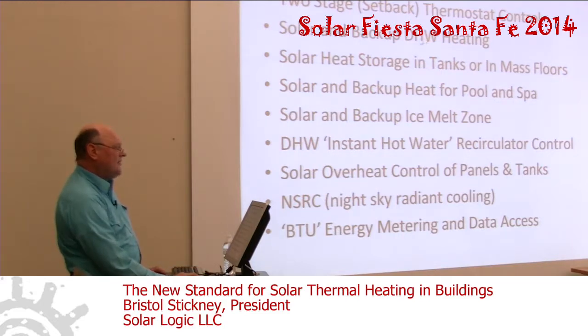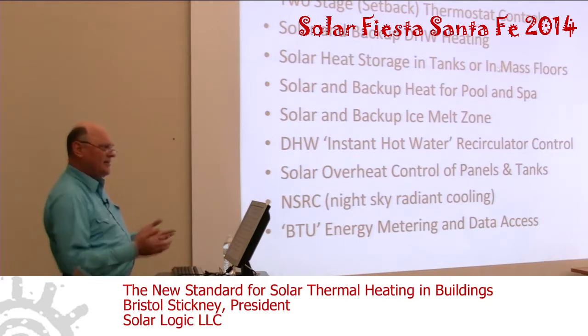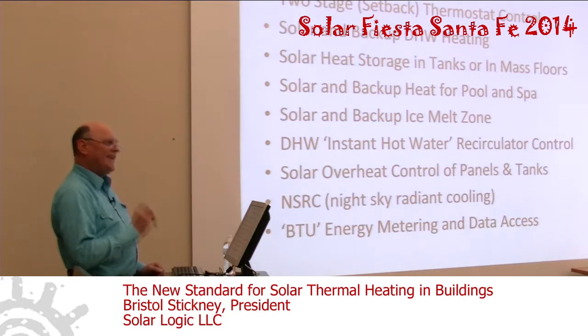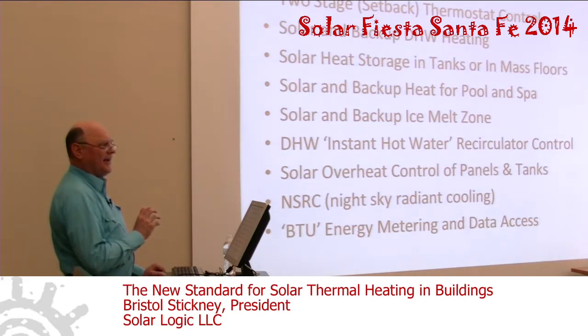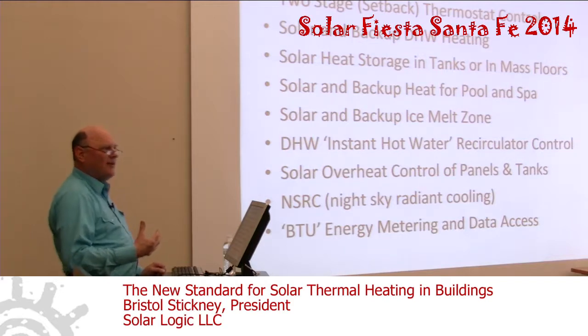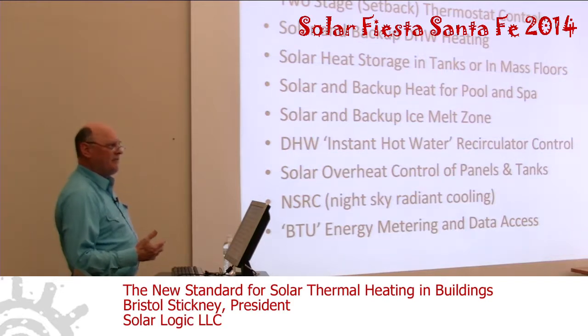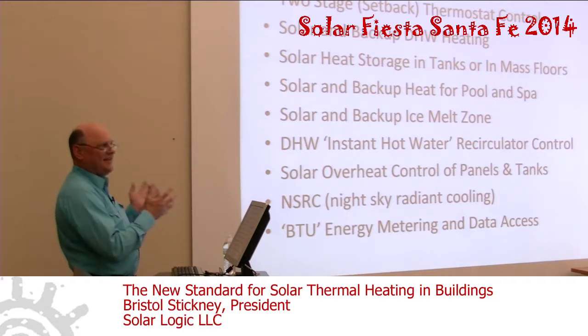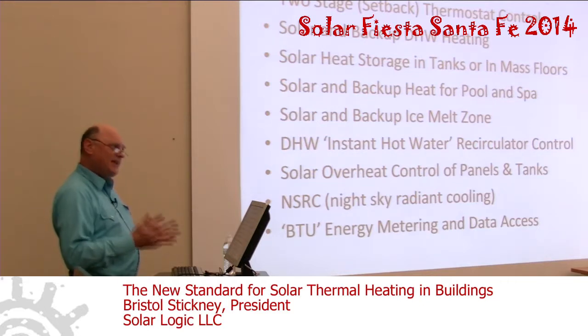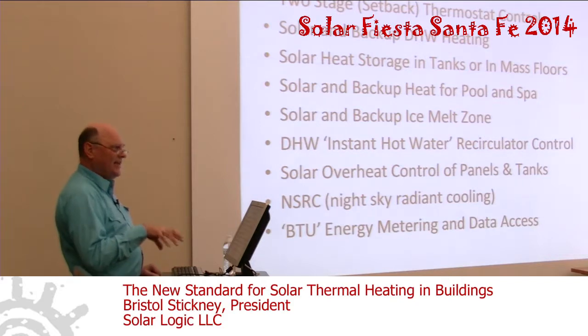You want the domestic hot water heater tank to be prioritized so that it gets solar first and the backup heat second. You want to be able to store heat not only in storage tanks, but also in any mass floors, like big concrete floors with heat being delivered into them, and control the heat stored in the concrete. And if you take that into account, sometimes you can eliminate the need for big heat storage tanks because all the heat that the collectors can put out can be stored in the thermal heat storage capacity of the concrete floor.